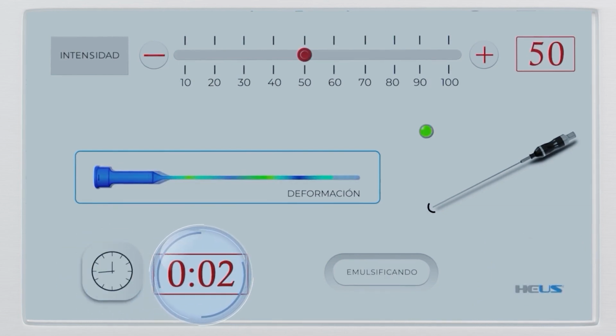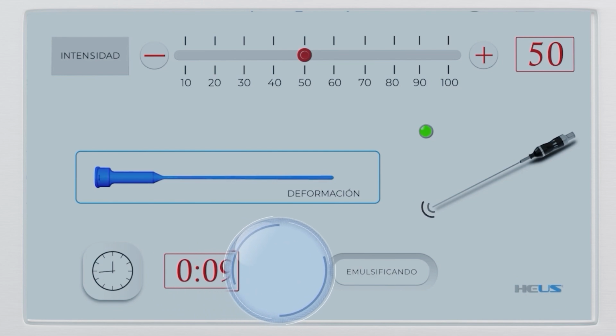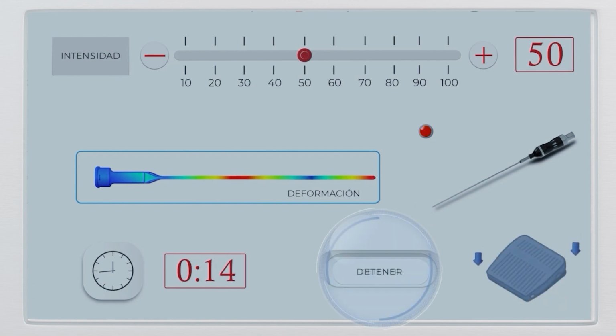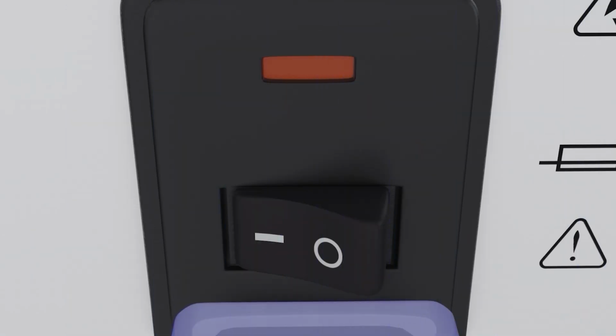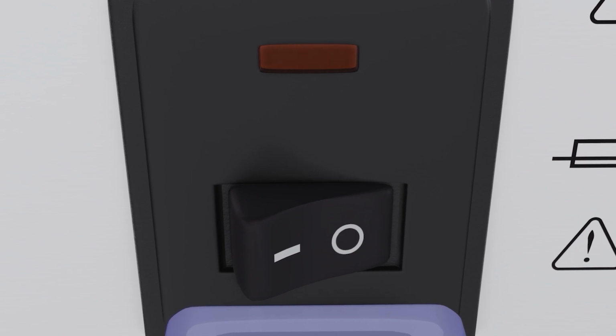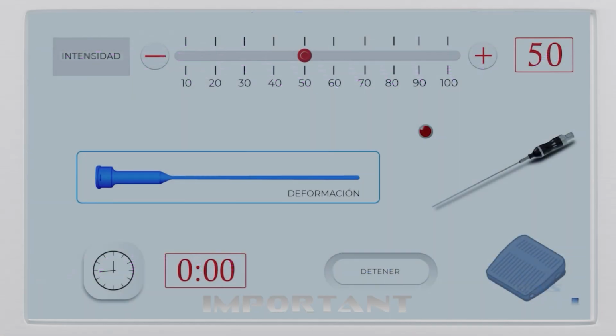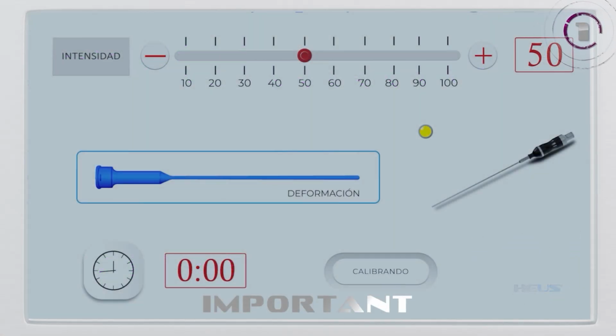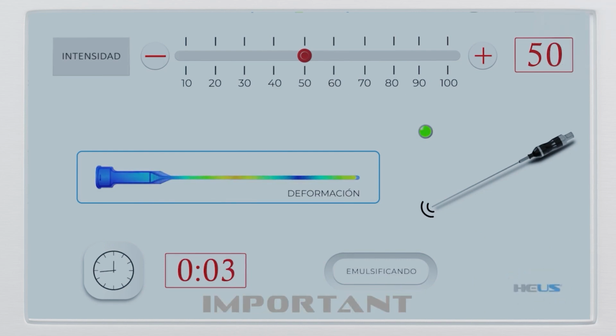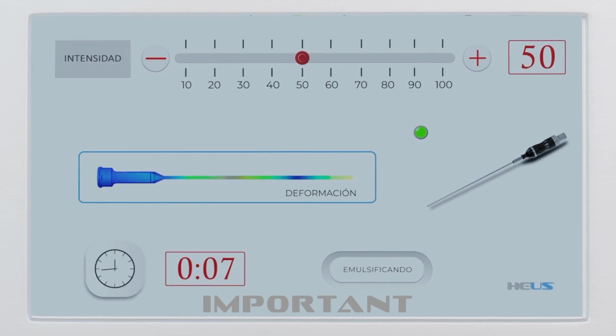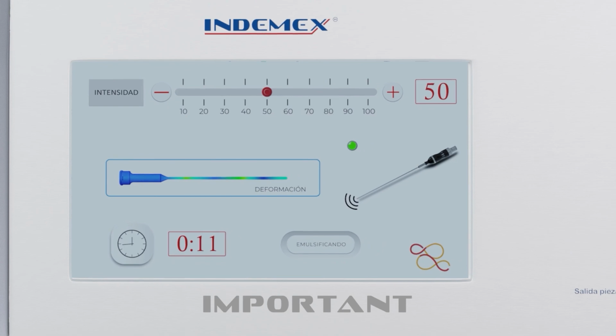Timer. This indicator is represented in minutes and measures continuous work within the session. It also serves as the method for analyzing the time used in each emulsification. To reset it, you must press stop on the screen. To turn off the device, deactivate the switch located at the back. It is important to consider: if the device is not used for more than a minute, pressing the pedal again will activate a short adjustment process, as it is necessary for the console to continuously measure the tissue hardness to be emulsified.